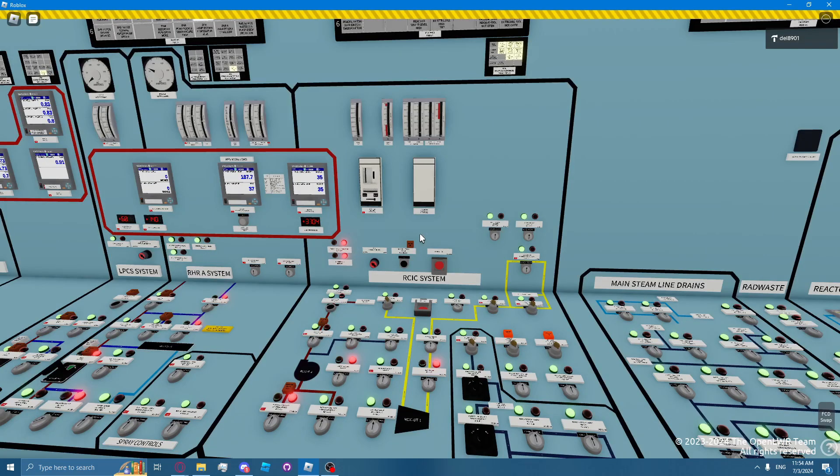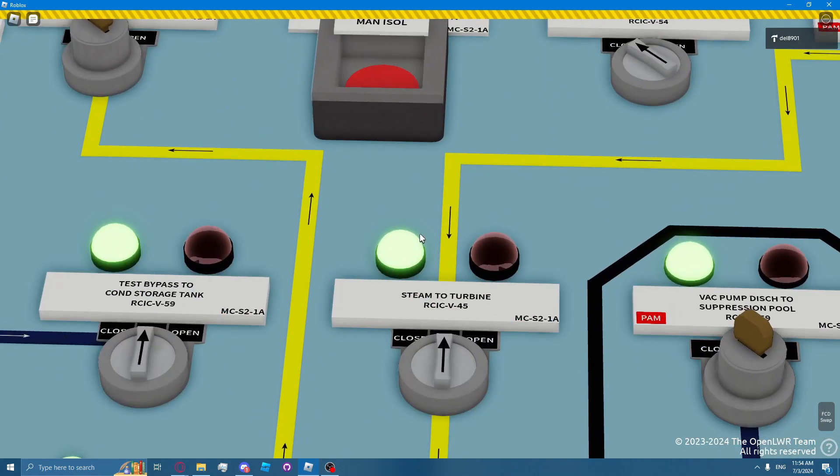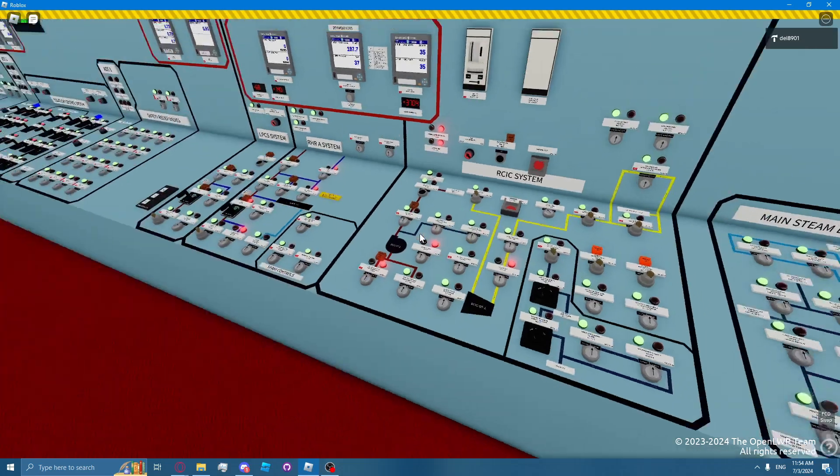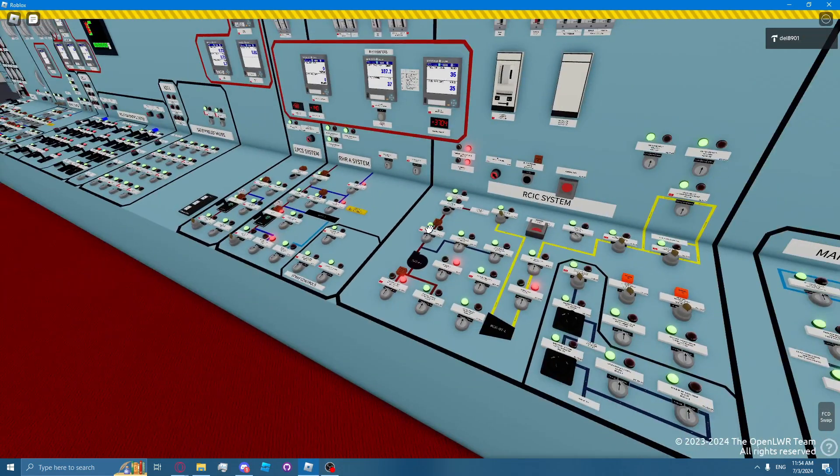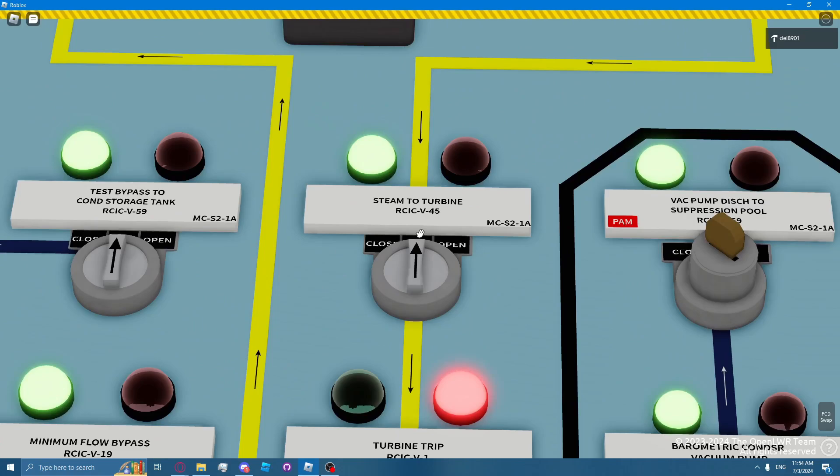On system automatic initiation, the steam turbine valve, RCIC valve 45, opens to supply steam to the RCIC turbine. RCIC valve 13, which is the RPV injection valve, opens when both RCIC valve 1 and RCIC valve 45 are open.